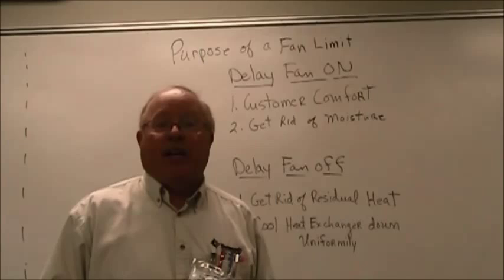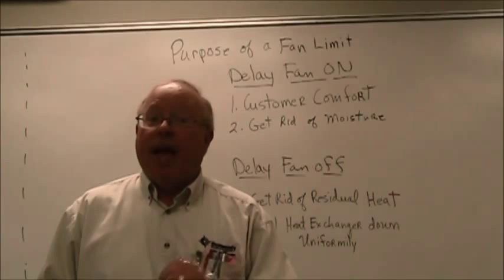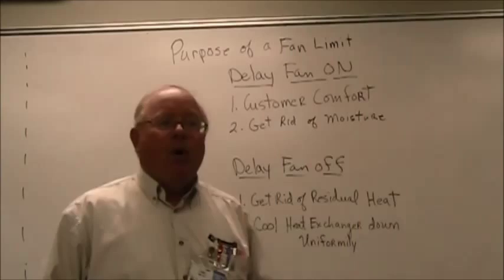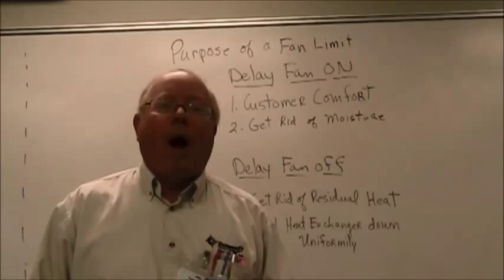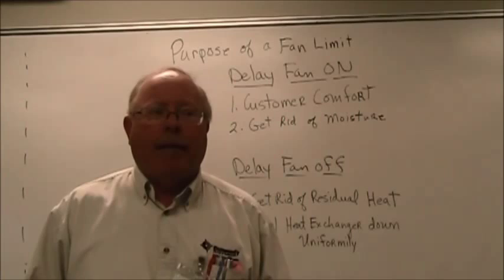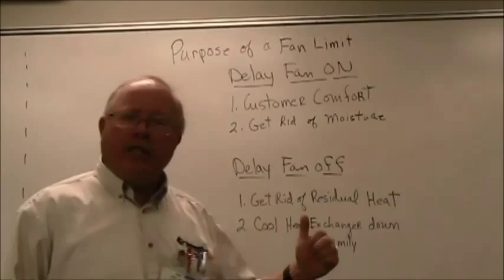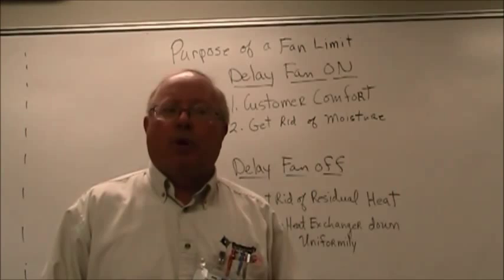Now, why do I want to shut the fan off in a delay? Many of you have probably noticed that when a burner shuts off on a furnace, the fan continues to run afterward for a short period of time. The purpose for delaying the fan off is to get rid of the residual heat. I've paid for that gas, I've paid for that heat — why would I want to let it go up the chimney and try to warm the state of Minnesota during the wintertime? So let's keep the fan running and get the heat out of the furnace and into the house where it's usable and saves me money.